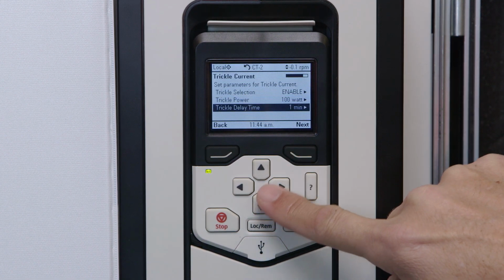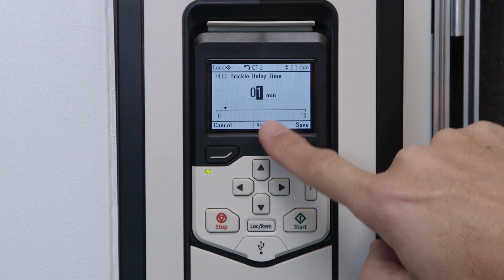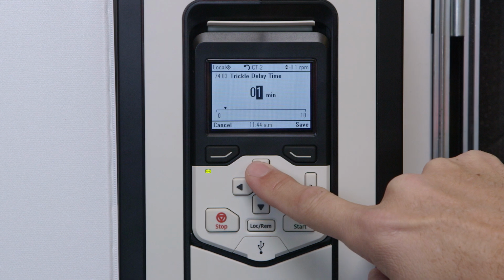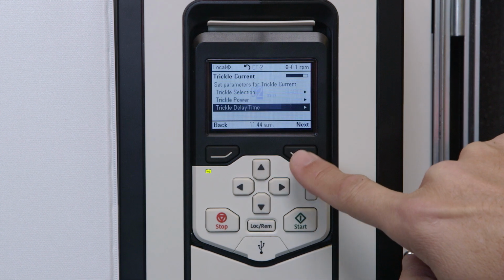Now, select the delay in starting the trickle current after the motor stops. The trickle current will begin after the motor stops plus the delay time. The default value is 1 minute. Once the delay time is entered, press Save. Then press Next.